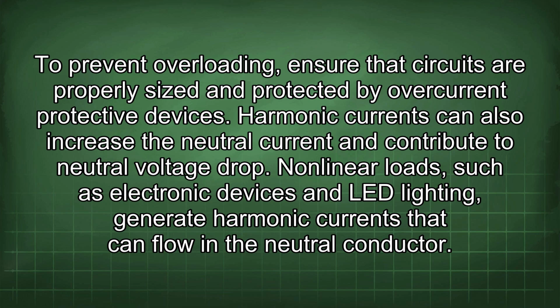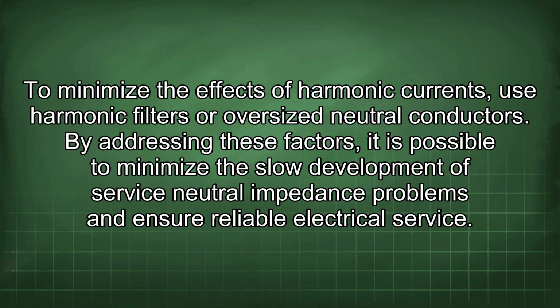Harmonic currents can also increase the neutral current and contribute to neutral voltage drop. Nonlinear loads, such as electronic devices and LED lighting, generate harmonic currents that can flow in the neutral conductor. To minimize the effects of harmonic currents, use harmonic filters or oversized neutral conductors. By addressing these factors, it is possible to minimize the slow development of service-neutral impedance problems and ensure reliable electrical service.